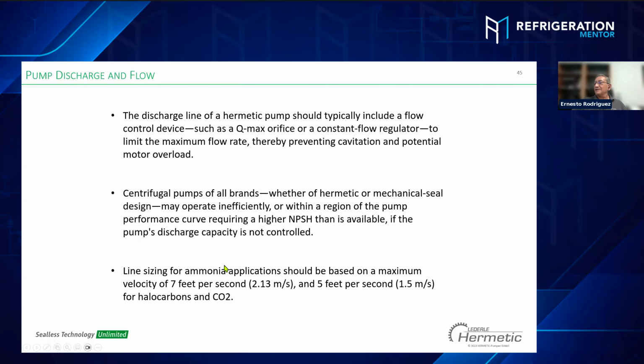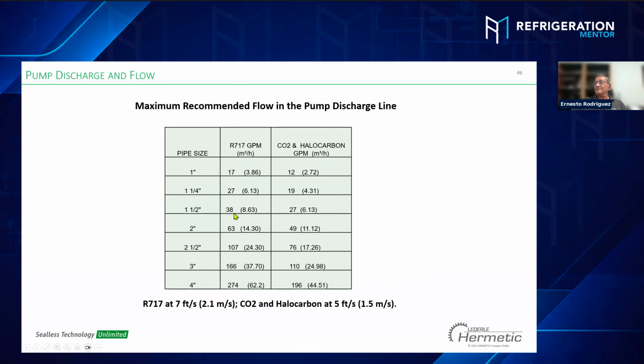Basically, on this discharge line, we need to keep 7 feet per second for ammonia and 5 feet per second for CO2. Okay, basically, we need to have a steady flow to our system, to the head, to the train of valves, to all the system, to the evaporators, which means the pump needs to run perfectly. We have this table. Okay, this table is for CO2. It's 5 feet per second, the velocity you require to move enough liquid all the way to your system.